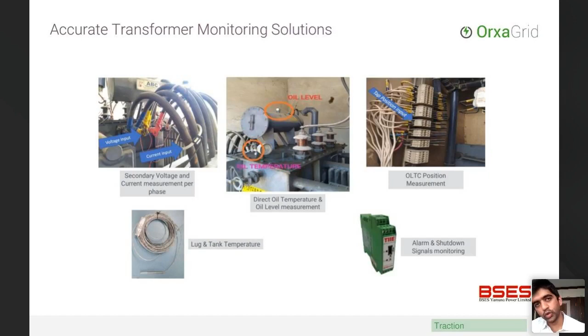Lug and tank temperature is also very simple. These are just PT100 inputs that can be installed on either of the lugs and so on. And then of course all digital inputs through CMR contact multiplying relays, where we can take in all these inputs from various points and then display those to any remote customer as well.